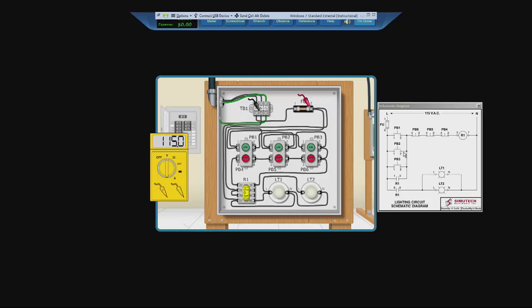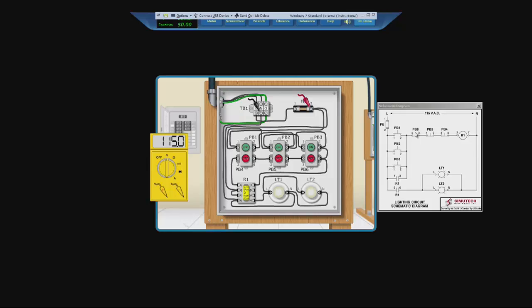So the next problem could be that a push button is shorted open. One of the stop push buttons, PB5, PB4, and PB6. The relay could be broken. Or relay one may not be getting power. Or there could be a wire not working somewhere.